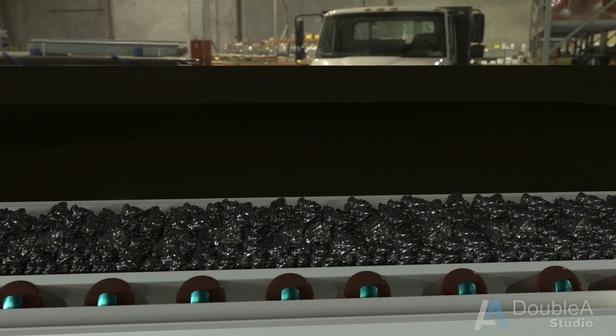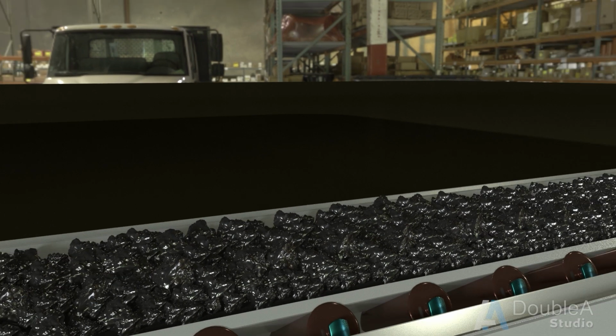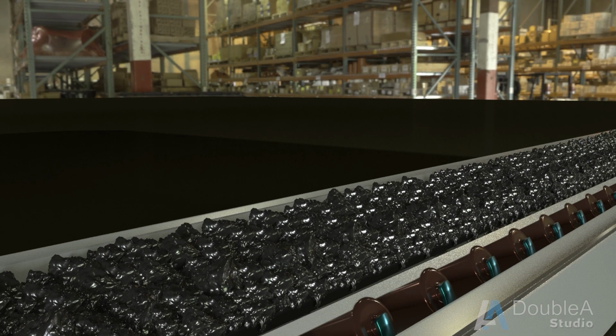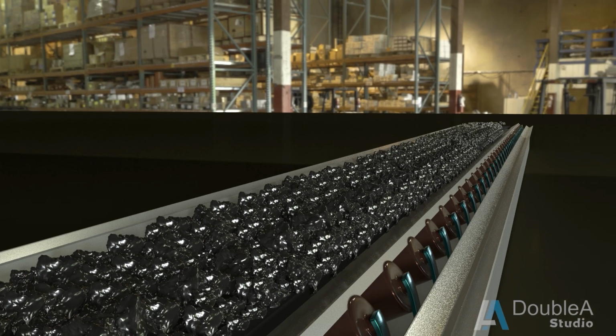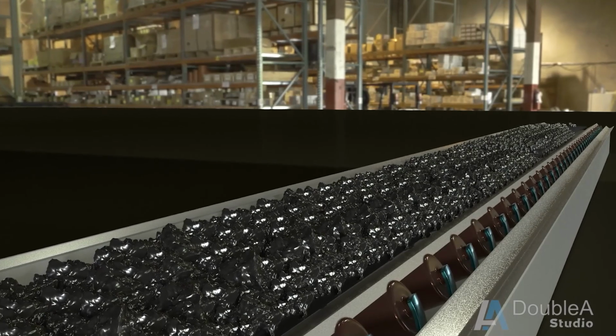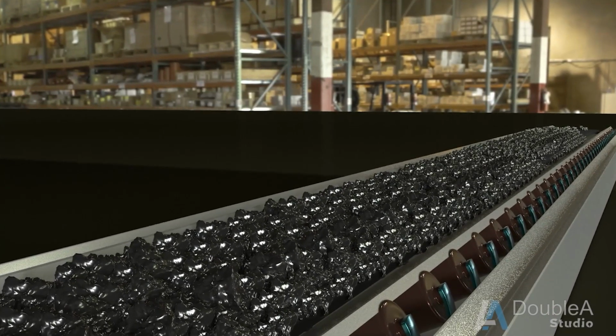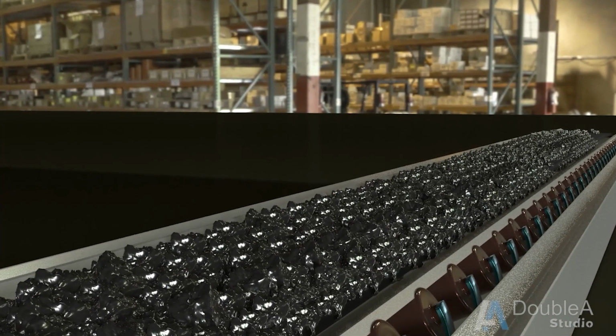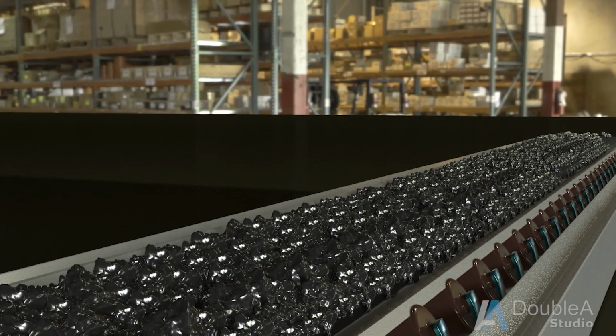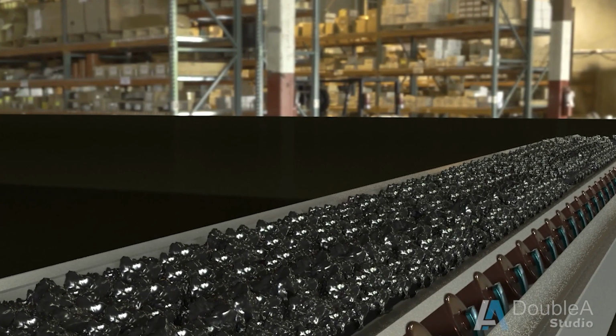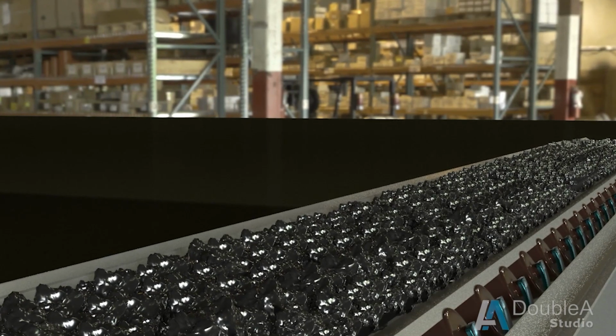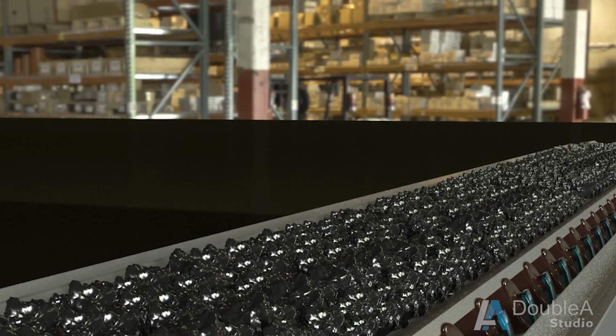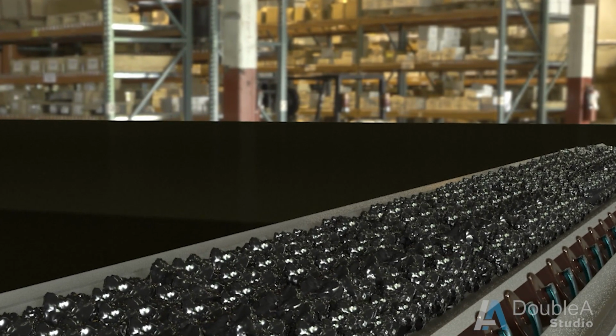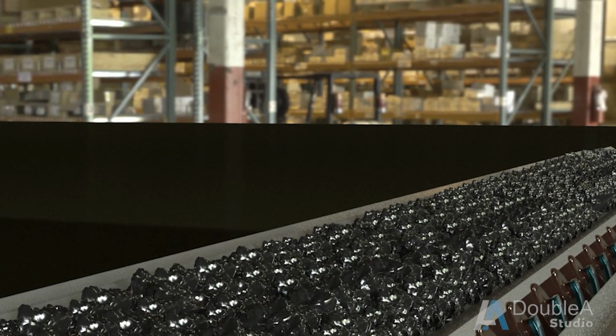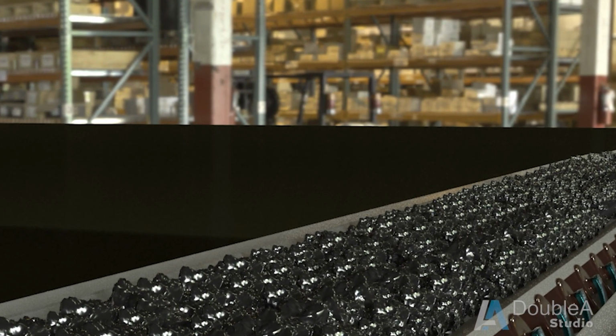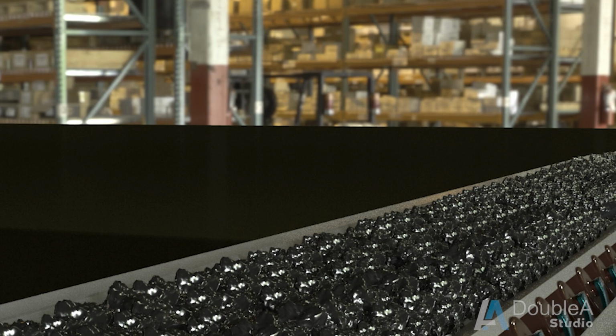Feeder plays an important role in evacuating coal from the hopper. For instance, if there is no feeder, coal discharge to conveyor belt may be erratic. If it gets coal which is lesser than its capacity, then it will run at partial load. In the other case, it may receive excessive coal which will overload the belt and may cause spillage and even failure. The feeder, therefore, feeds the correct amount of coal for its optimum performance.